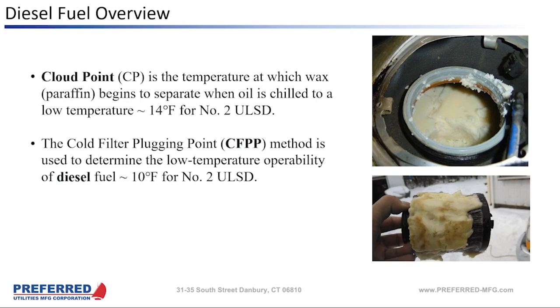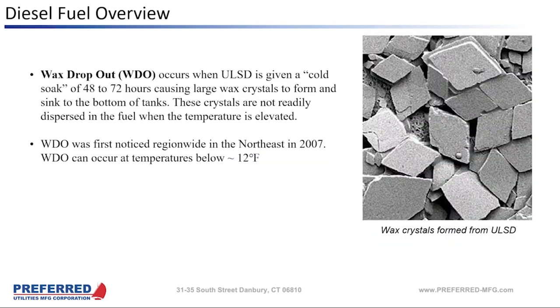And we've got pictures here on the right of clogged strainers and clogged filter elements from diesel that's gelled, gotten below its cloud point. For the most part, David, would you say that when we're looking at filters getting plugged like that, that's going to be on the generator end? I mean, other than polishing units, we really don't have filters that are that tight on the back end of most fuel systems.